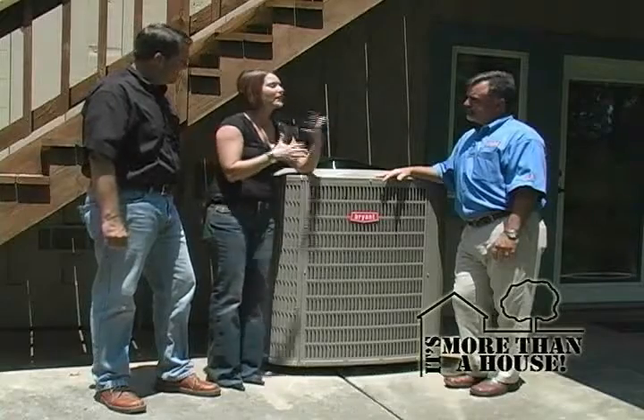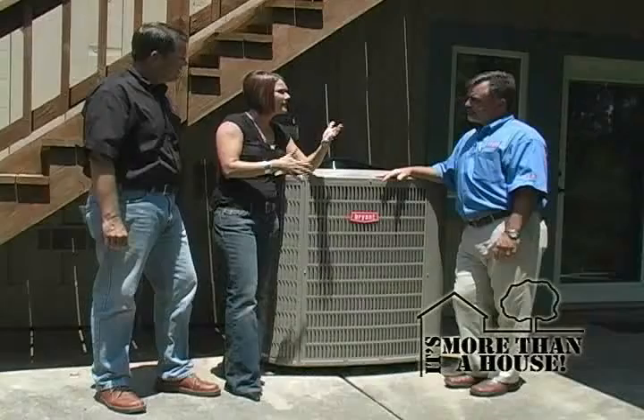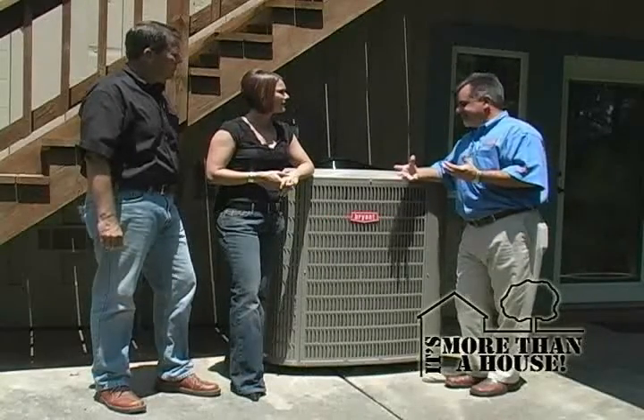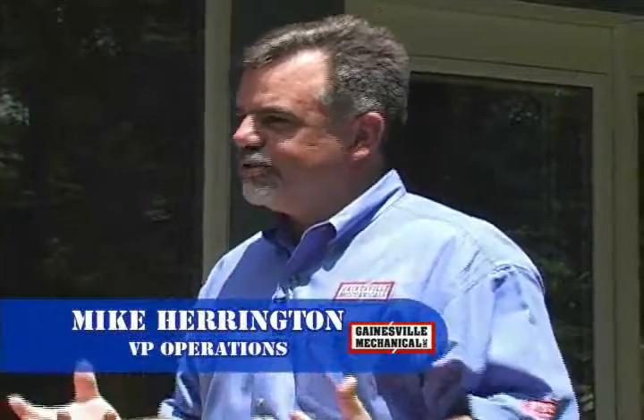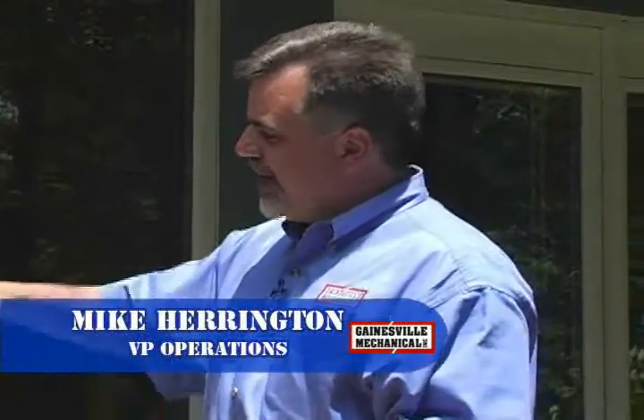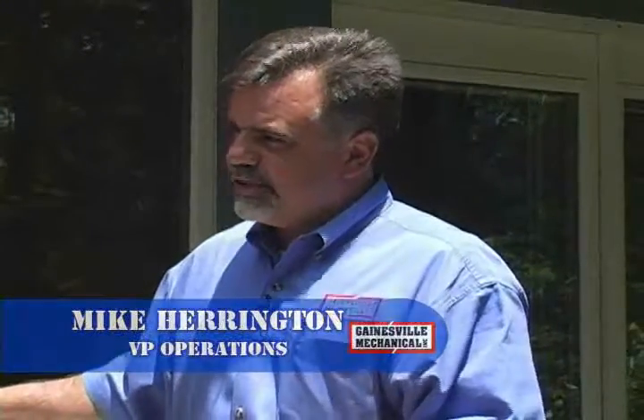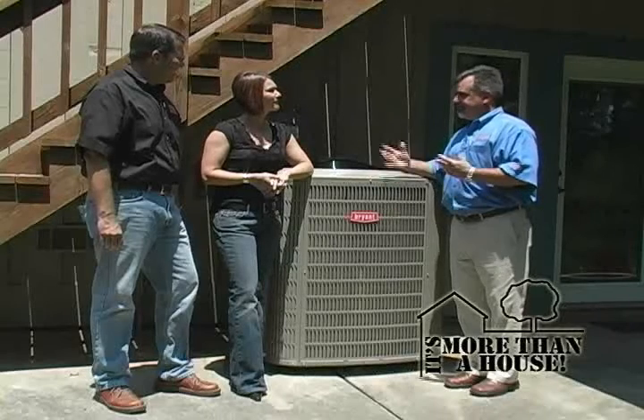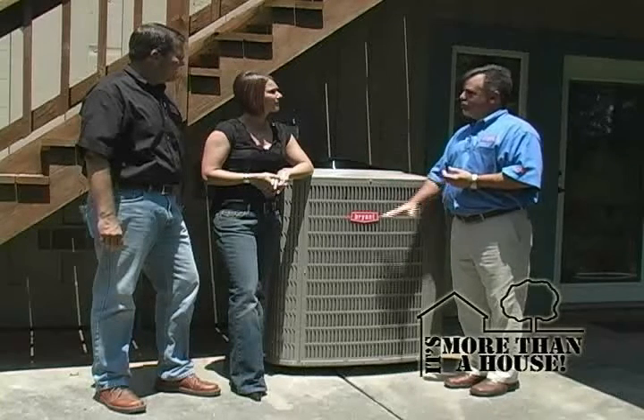I'm not real sure when you talk about it running on 5 tons or 3 tons — I don't understand what that means. Well, a ton is considered as 12,000 BTUs. It takes a ton of air conditioning to remove 12,000 BTUs of heat. So 5 tons would be 60,000 BTUs of energy being used. But most of the time you don't need full capacity, so it runs on low speed — 85% of the time on low speed and then the other 15% on high speed.